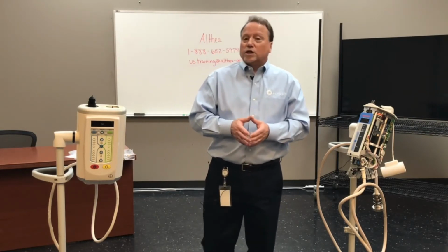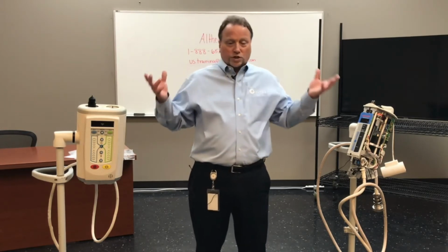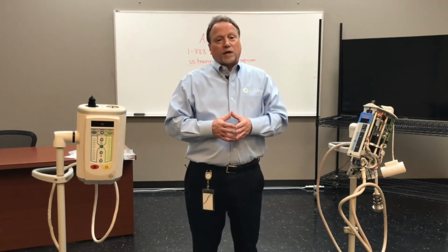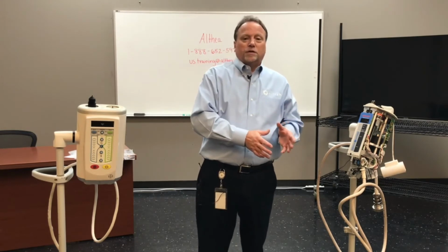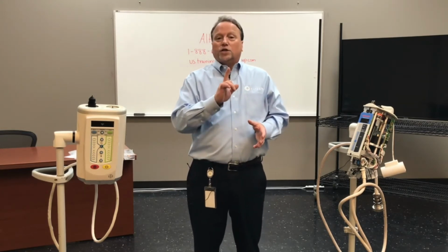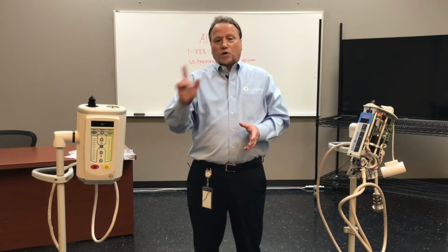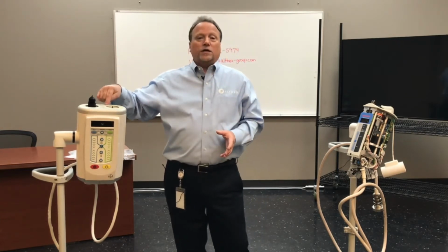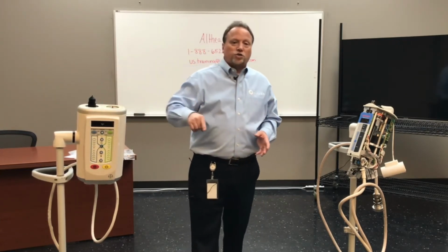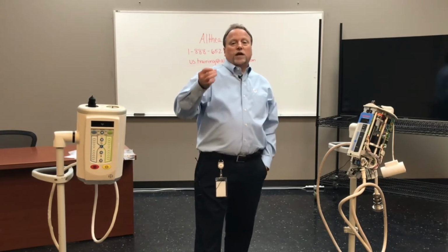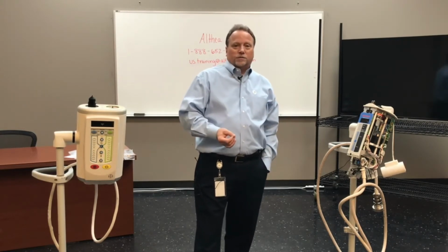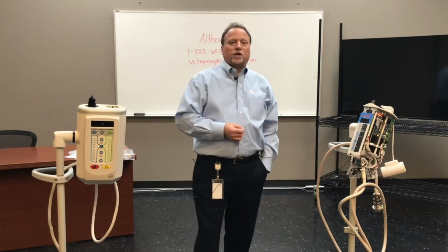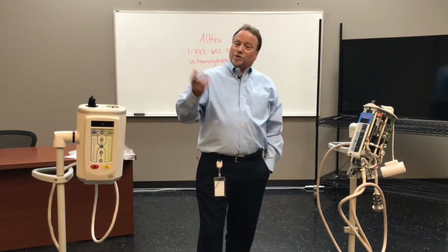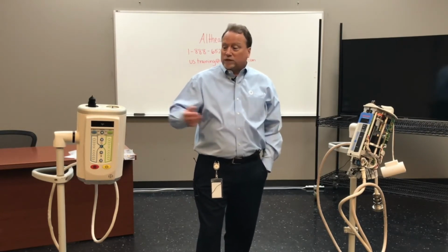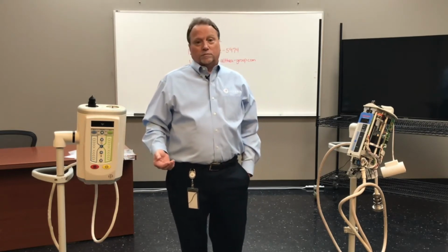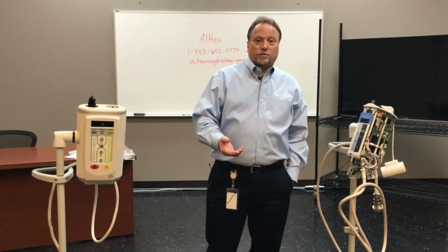And maybe instead of an annual PM, as all these injectors require, maybe it's a quarterly PM, just to keep it clean. Because remember again, the number one issue of causing problems with the injector is contrast. Contrast intrusion. Contrast and saline are conductive. So when it gets on a board, it shorts out the boards. When it dries, it's no longer conductive. But what damage has it caused to that board? They are conductive.